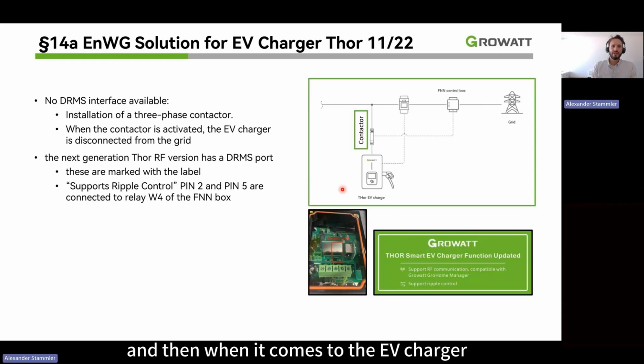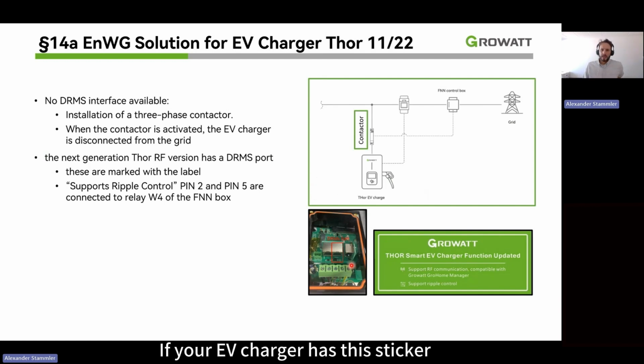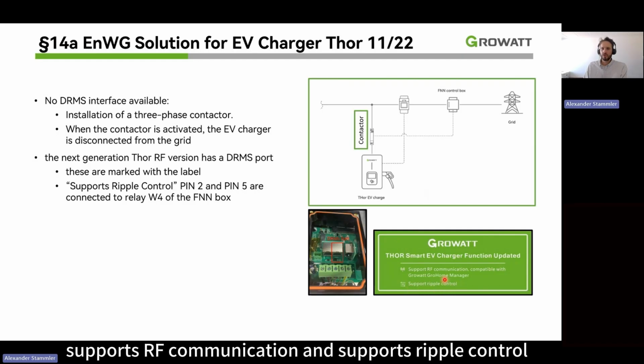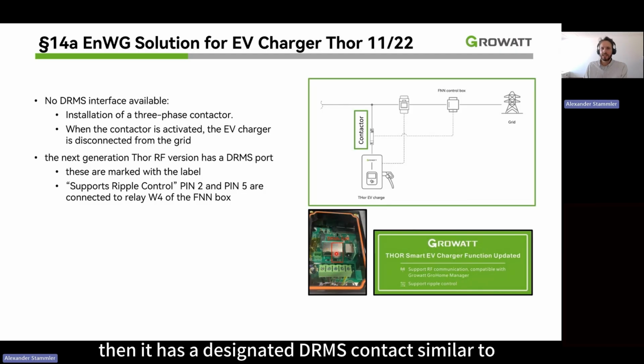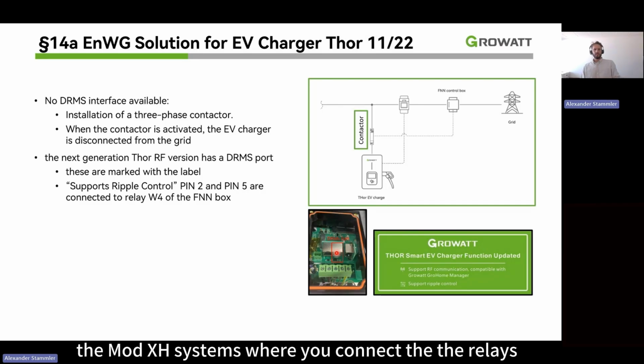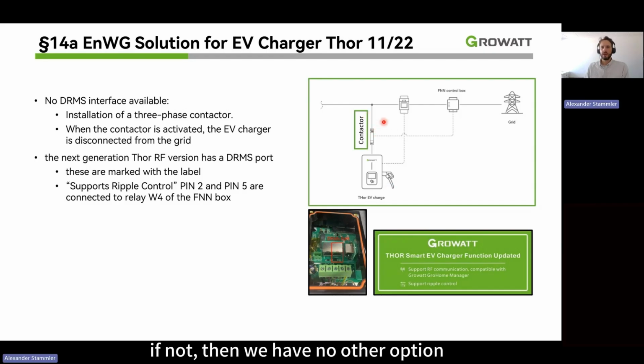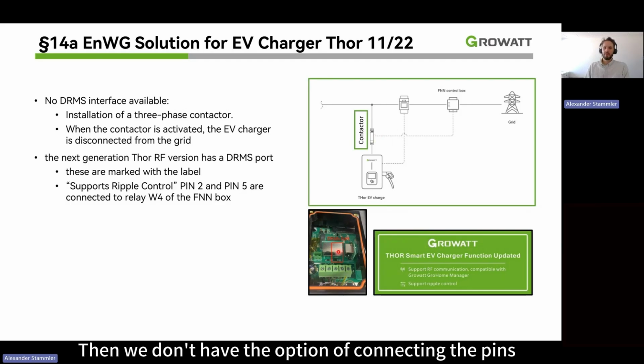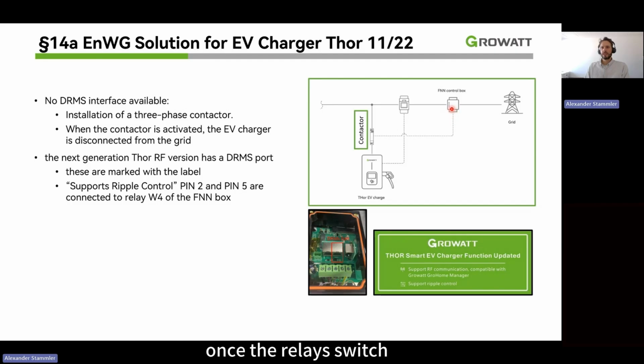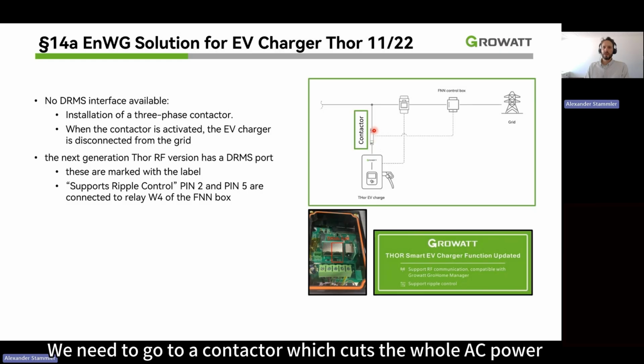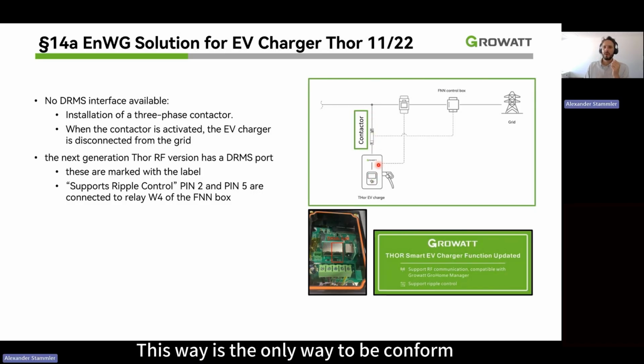And then when it comes to the EV charger, we need to do the same. If your EV charger has this sticker, supports RF communication and supports ripple control, which is the important part, then it has a designated DRMS contact, similar to the Mod XH systems, where you connect the relays. If not, then we have no other option, especially the ones that are already installed. They usually don't have this. Then we don't have the option of connecting the pins. Then what we have to do is the control box, once the relays switch, we need to go to a contactor which cuts the whole AC power towards the EV charger. This way is the only way to be conform with paragraph 14a of EnWG.